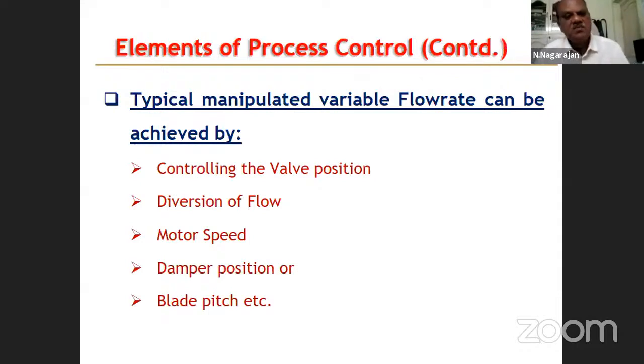Damper position comes in the fired heaters where flue gas is going out of the fired heater in a stack. There we put a valve. Damper is nothing but another valve. So you can adjust the damper position to allow the inlet air coming into the heater. That way you can control the heat transfer rate. Blade pitch is again for the fan. The fan blade pitch can be changed to vary the flow rate of the air. But blade pitch can be done only during maintenance. It cannot be done during the operation. The other 4 parameters listed above can be done during the operation.